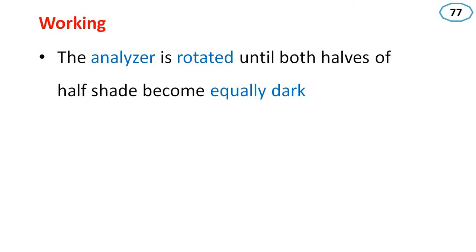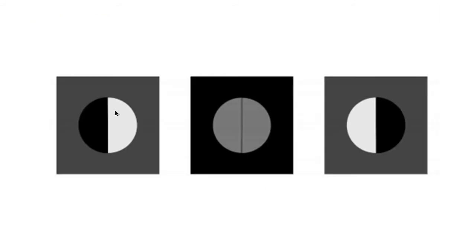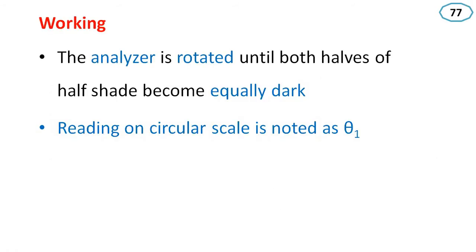The analyzer is rotated until both halves of the half-shade plate become equally dark. In the polarimeter you can see a circle: half of the circle will be dark and half will be bright. When we rotate the analyzer, there is a position where both halves are equally dark — this is the second figure condition. We rotate it to this position where both halves are equally dark. The reading on the circular scale is noted as theta 1.